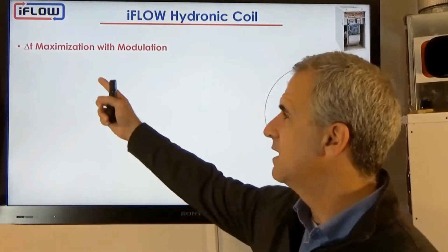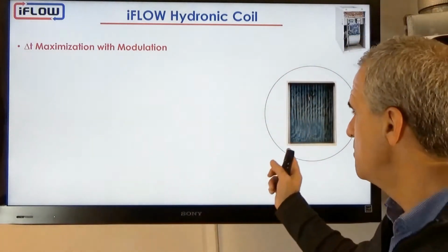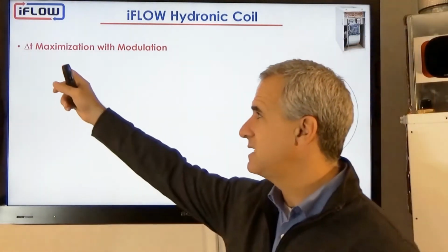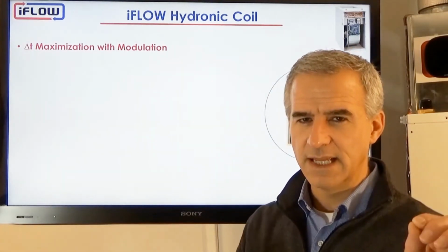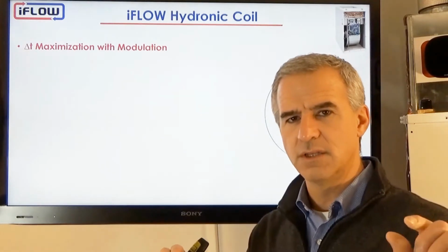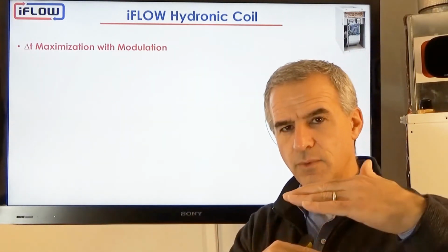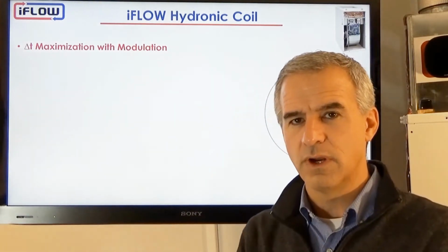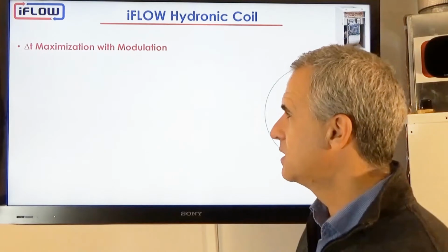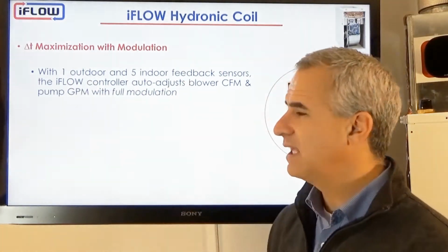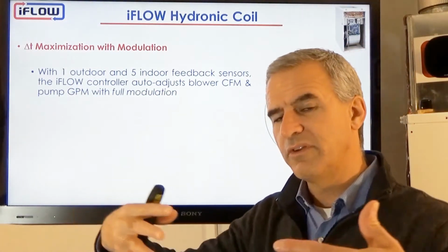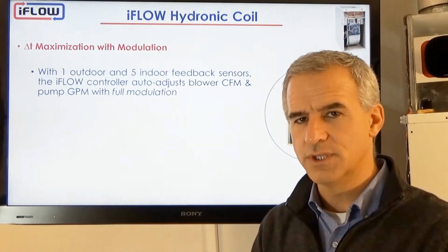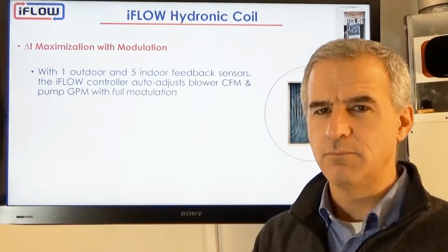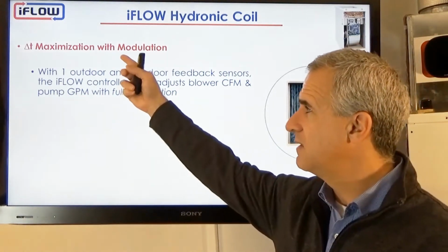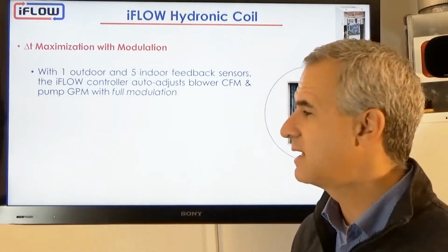Our strategy is for delta T maximization with modulation. So we're trying to maximize the temperature differential. A delta T is the change in temperature from the inlet to the outlet. So we look at the temperature coming into the unit and the temperature going out of the unit. The further we can spread that means the more heat is going into the air, and likely the more efficient the performance of the heat source will be. So we have 1 outdoor sensor and 5 indoor feedback sensors that all feed back to the controller, and then the controller auto adjusts the CFM rate and the pump speed to achieve this delta T maximization or efficiency maximization.